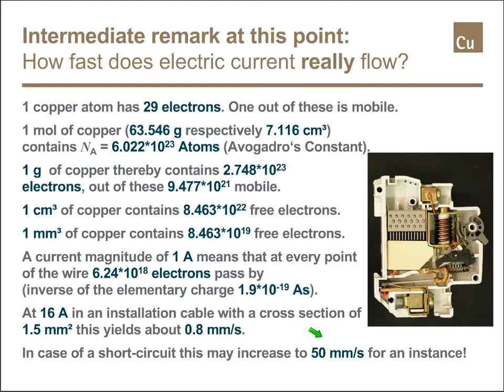Let's go down to 1 cubic millimeter, then it's 10 to 19, and the current of 1 amp, you must know, always means that at a particular point in the wire, 6.24 times 10 to 18 electrons pass by. This is the inverse of the elementary charge of 1.6 times 10 to minus 19 amp seconds or coulomb. At 16 amps in a home installation wire, in a building wire, size 1.5 square millimeters, this yields a speed of the actual motion of electrons of 0.8 millimeters per second. That is not really so much. When a short circuit occurs, it may increase to 50 millimeters per second, but that's really all. So electricity is not really very fast in physical terms.